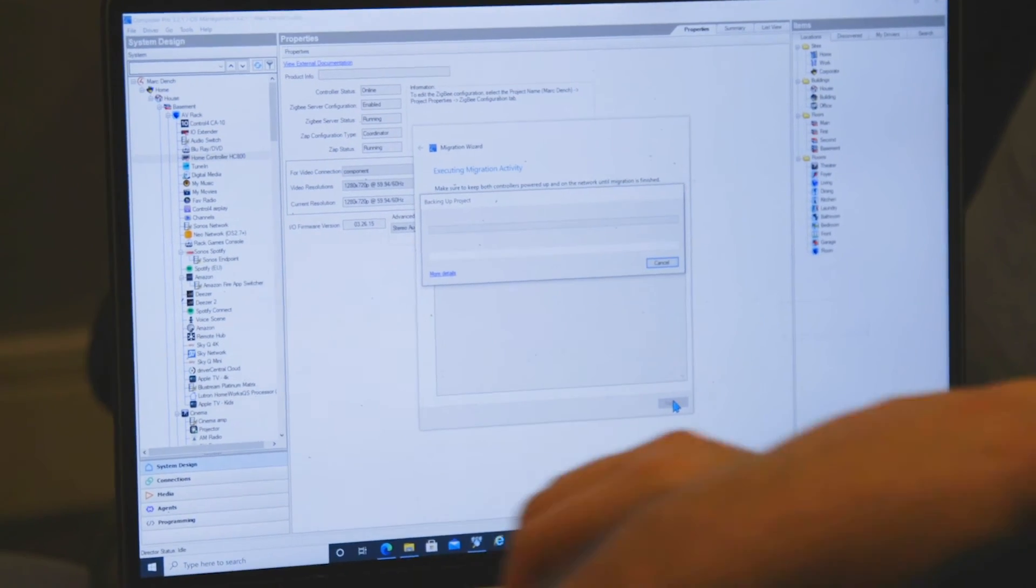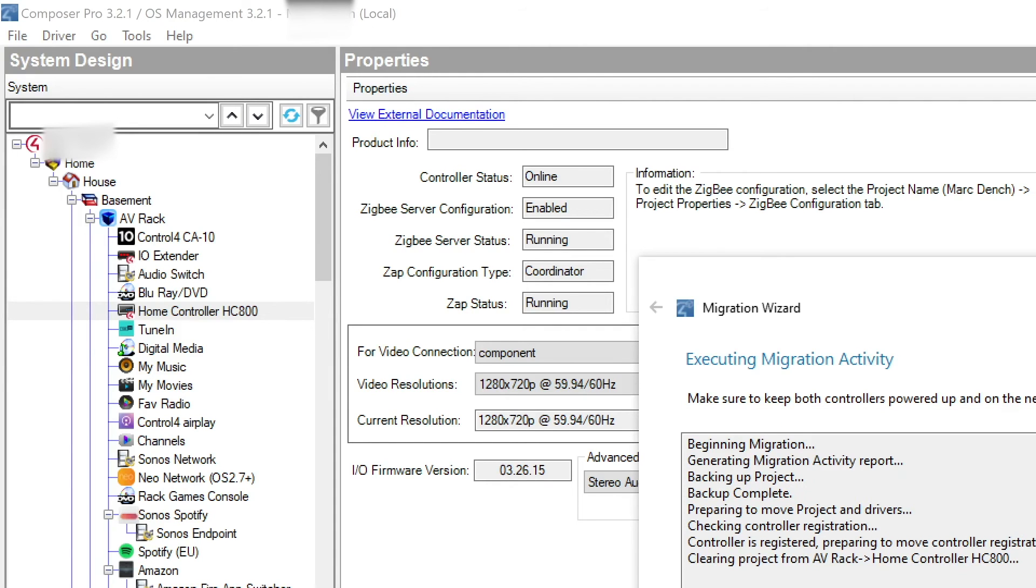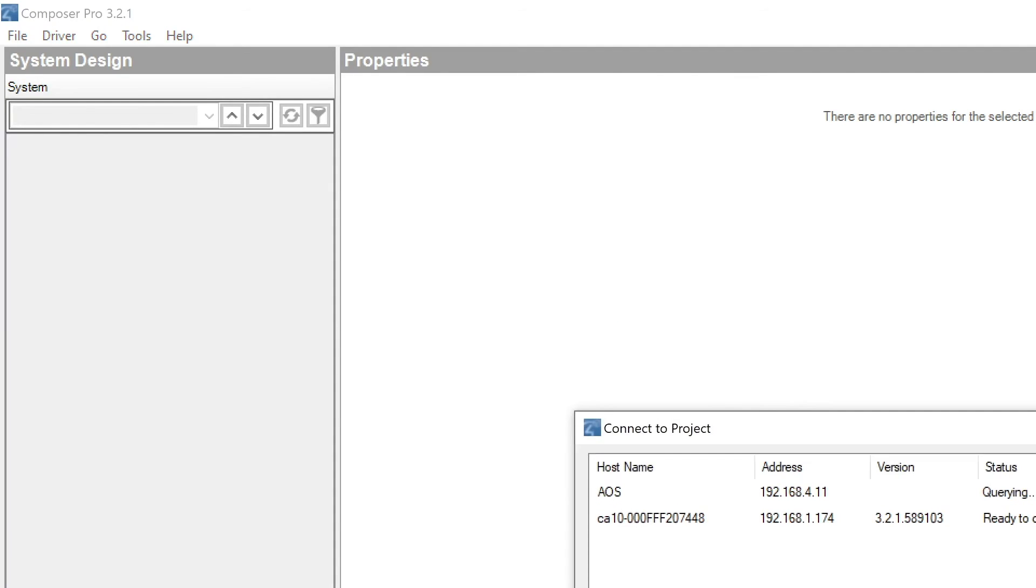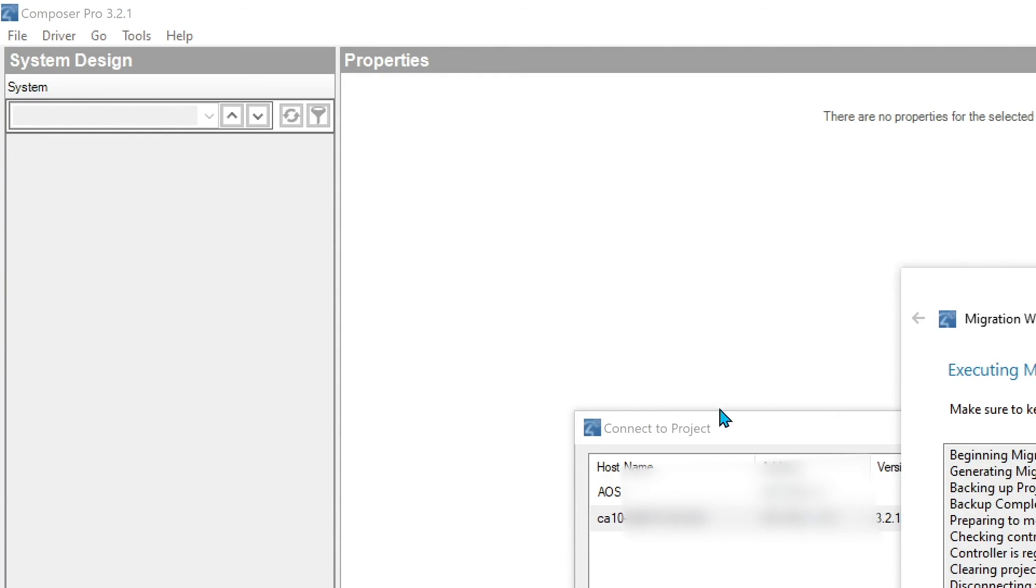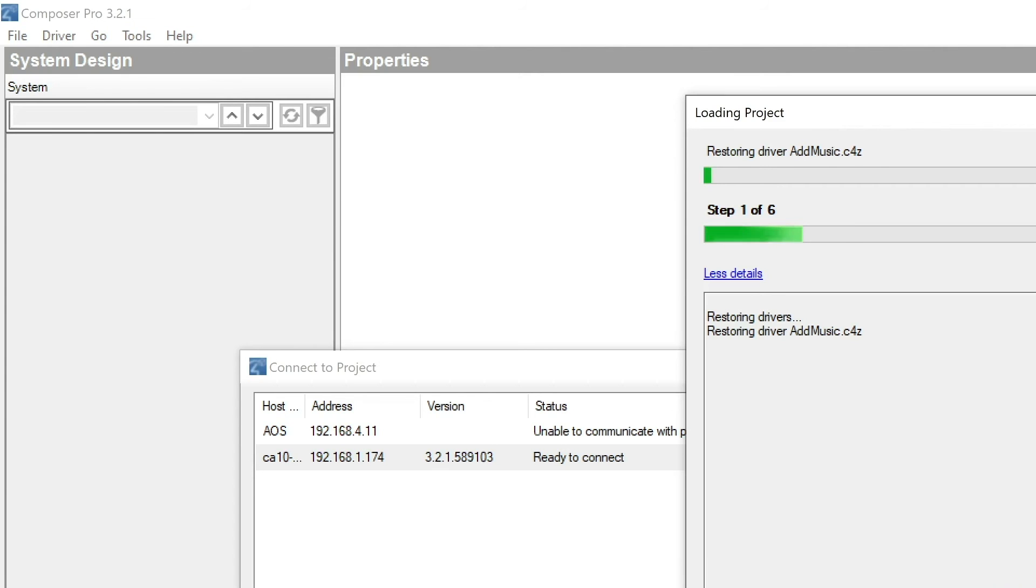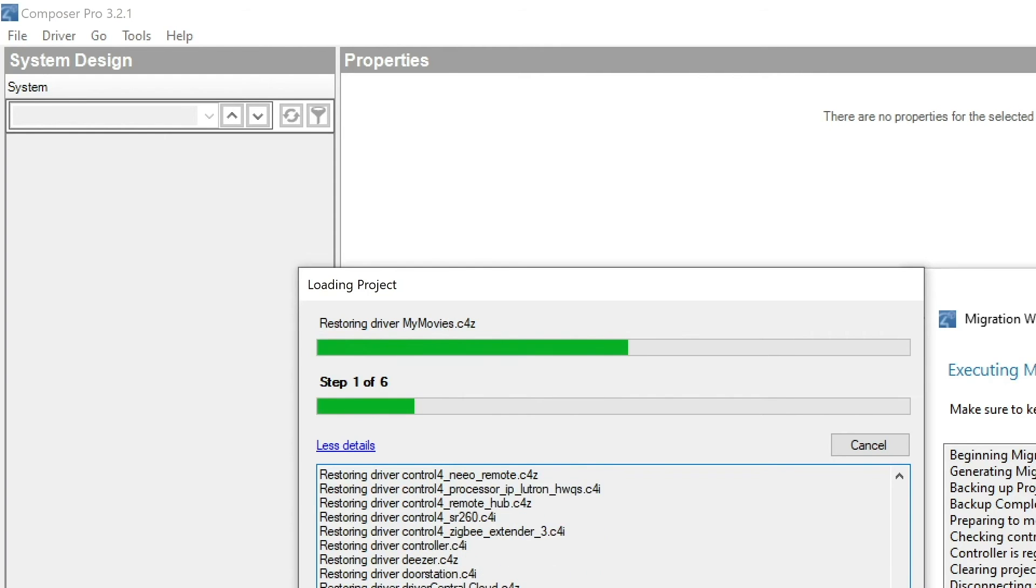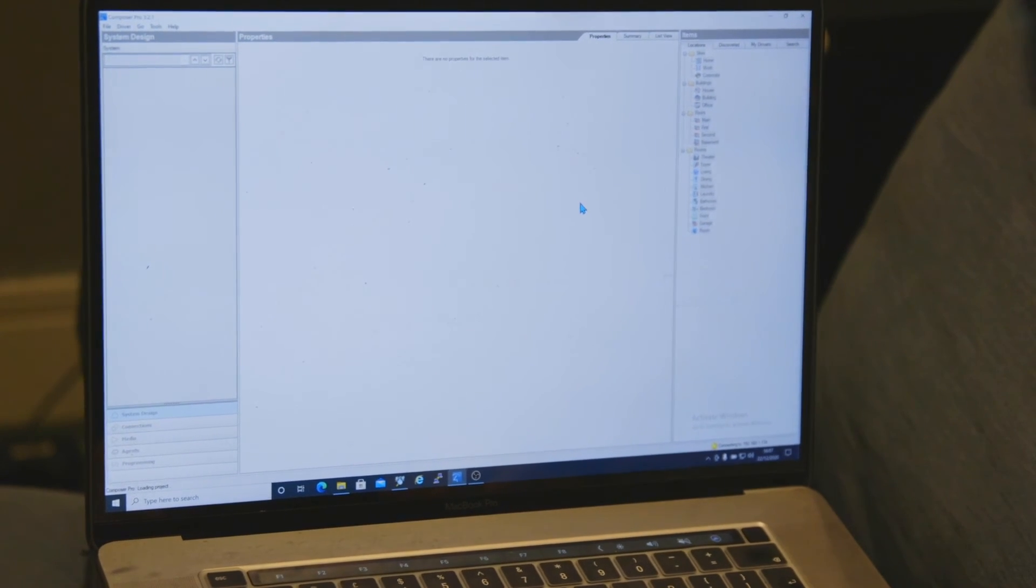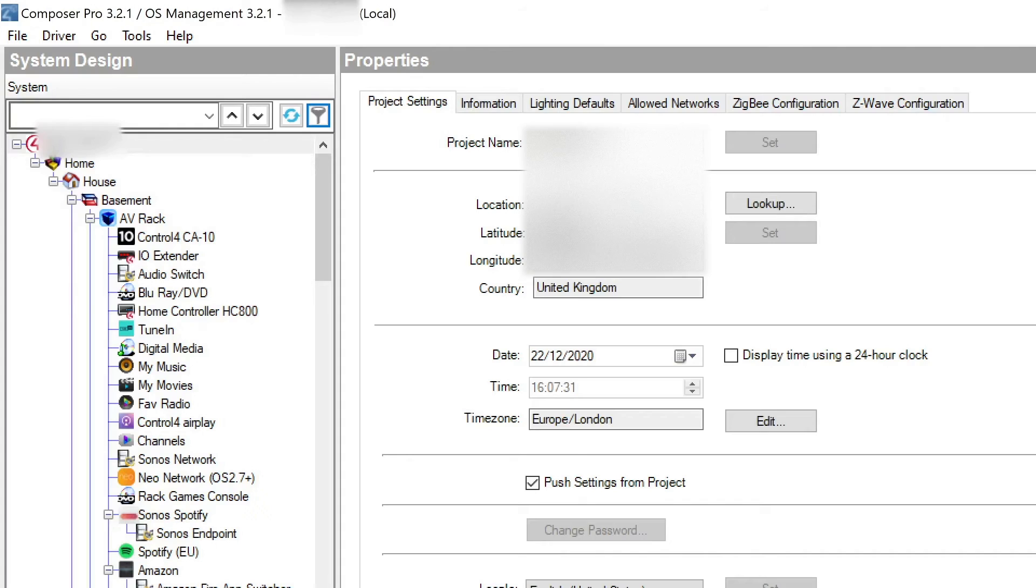It's then going to do a second backup, which is fine because we've just updated the OS. So if you're in Composer Pro, it should have enabled director from the CA10, and the CA10 should be available from the available controllers list. So there, the controller there is now running director, and we'll connect until it's finished its migration. But it's sat there waiting to go. And we can connect onto the processor, which as you can see even just by literally the loading process is faster. And there, we're straight into the project already, whereas that took about a minute before.